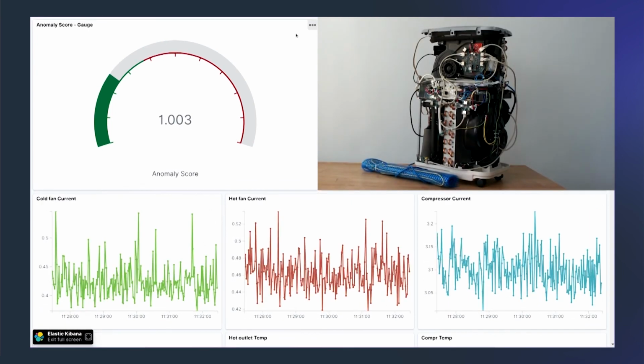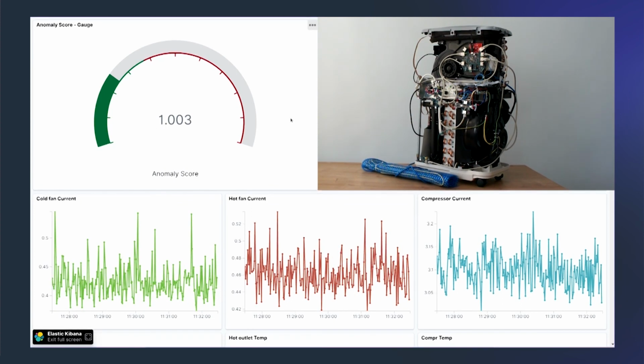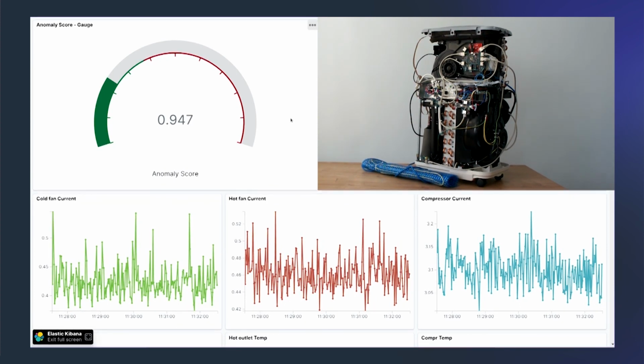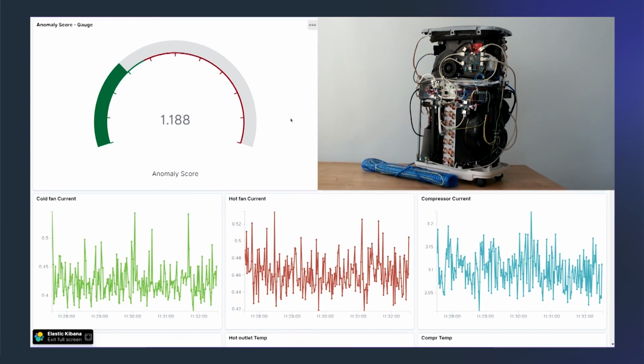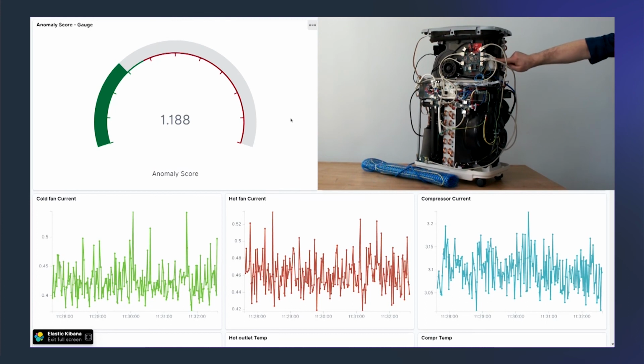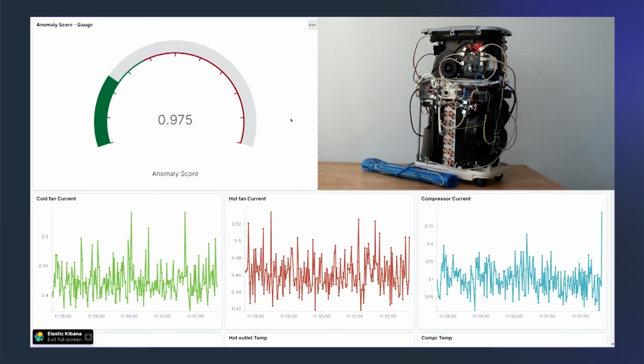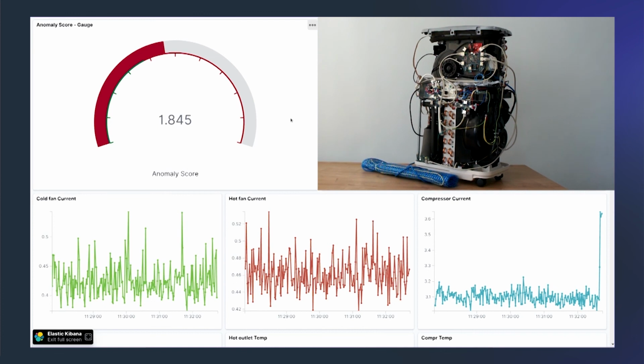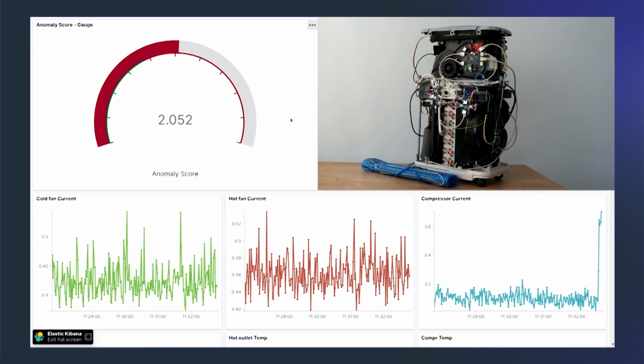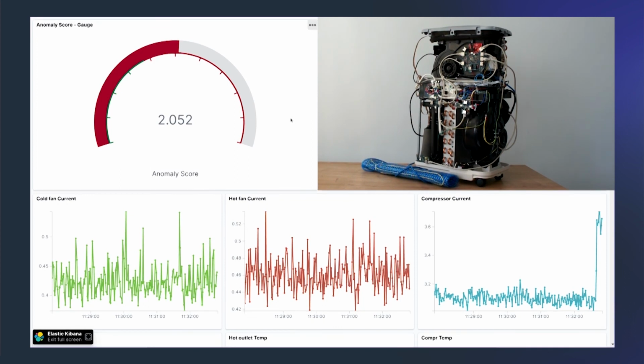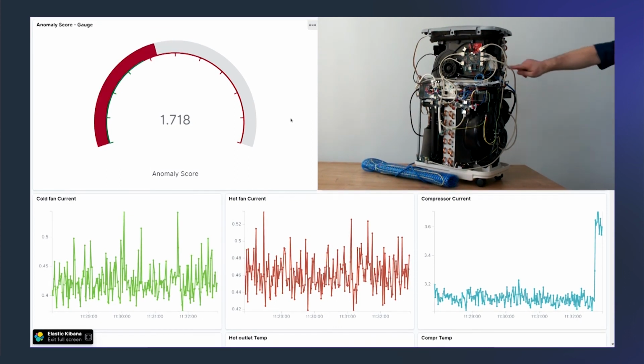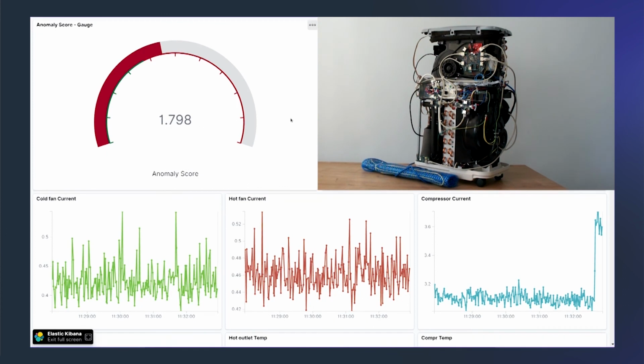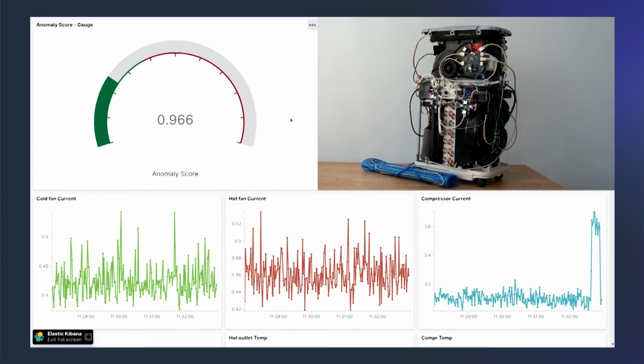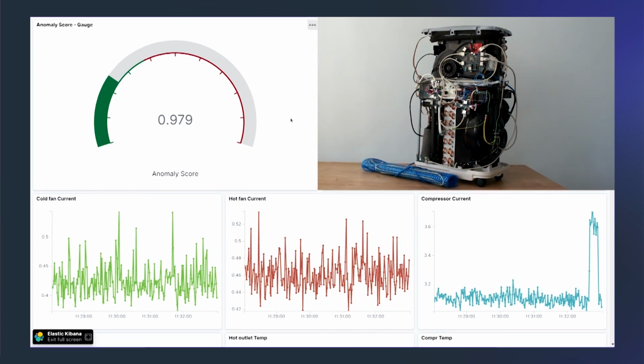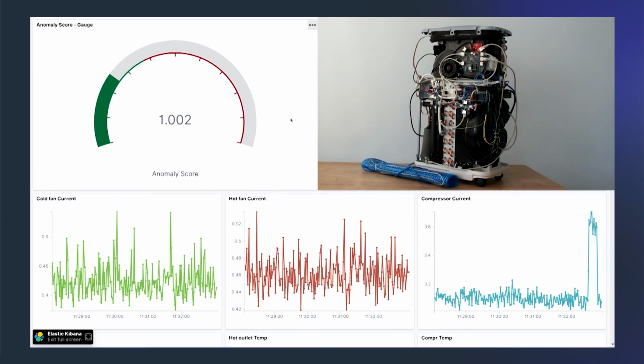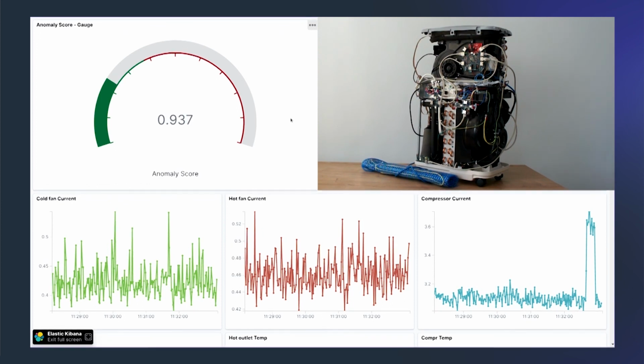In a second, we'll move to yet another demo. Here it is. It's a compressor anomaly behavior demo. At the beginning, the HVAC unit operates as expected. We have also connected a heating element to the compressor power circuit supply. It is on the table in blue color. Now we've switched it on, and you can see that the random cut forest algorithm identified the anomaly. Now we're switching off the heating element, and you'll see that almost instantly the system started behaving as expected. So those were the two demos that we planned to show today.